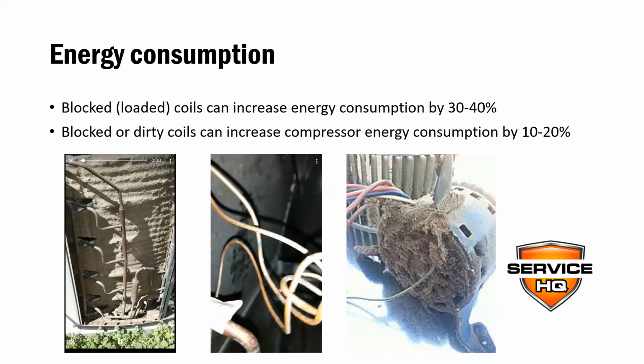And when those coils get loaded, it can increase energy consumption by 30 to 40%, which is insane, right? Blocked or dirty coils can increase compressor energy. Now, the compressor is in your outdoor unit, or if you have a package unit, it's in the package unit. But it's the heart of the air conditioning system. And if we have blocked or loaded coils, it's like having a blocked or loaded artery, kind of like it's just going to have to work a lot harder to just maintain.